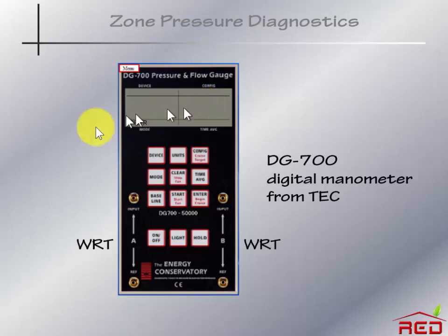Both of the manometers, the Energy Conservatory, pictured here, and the Retrotec manometer, are essentially two digital differential pressure gauges, one on one side of the gauge and another on the other side of the gauge. Something that is very important for me is to think of this pressure tap with reference to, that's what WRT is, this pressure tap. And likewise over here, this pressure tap with reference to this pressure tap. Remember, always with a manometer like this, you are measuring pressure differences from one space to another.